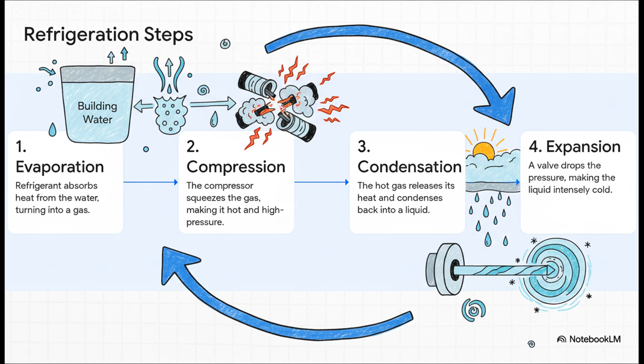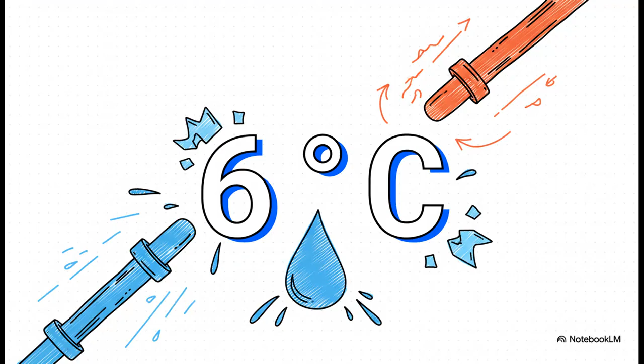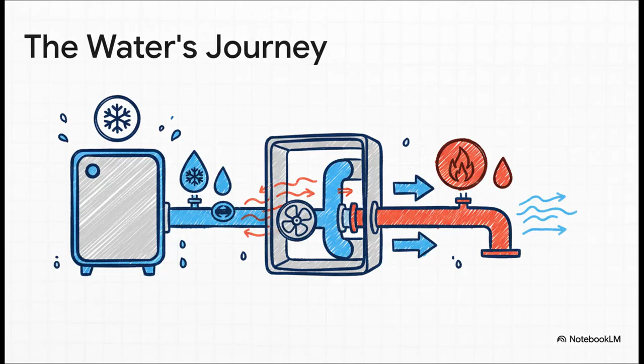Okay, so that's the magic happening inside the chiller. Now let's zoom back out and see how this heart connects to the rest of the building using that network of pipes we talked about. So the chiller's one and only job is to get a constant stream of water really cold. We're talking down to a target temperature of around a brisk 6 degrees Celsius. That's about 43 Fahrenheit. So now you've got this ice-cold water, and it's ready to go on its mission, hunt down and collect heat. And this is what we call the chilled water loop.